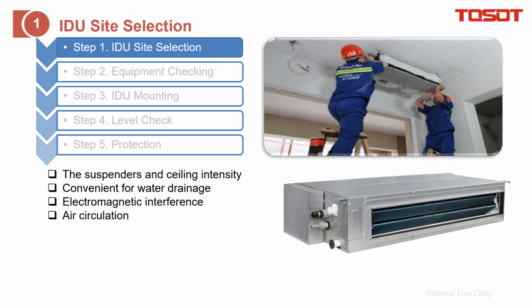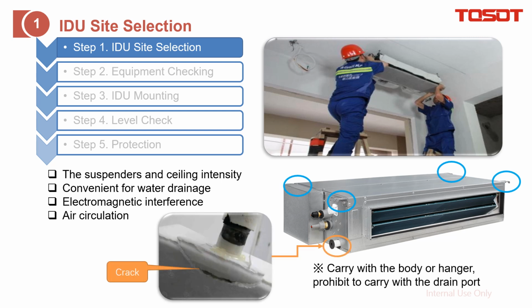And the next is to consider electromagnetic interference and avoid it, as it may affect the indoor unit operation, especially to avoid the indoor unit turning on automatically when there is no command. That is the reason. And the last is air circulation. That means in this area, the air circulation should be good enough. Besides, when you transport or lift the duct type especially, only hold these 4 areas. If you hold the drainage pipe like this, we are afraid it may crack, and this also leads to water leakage.